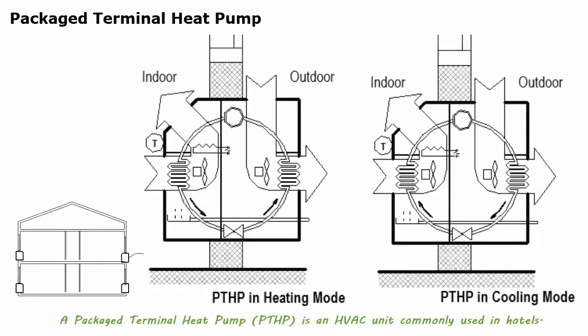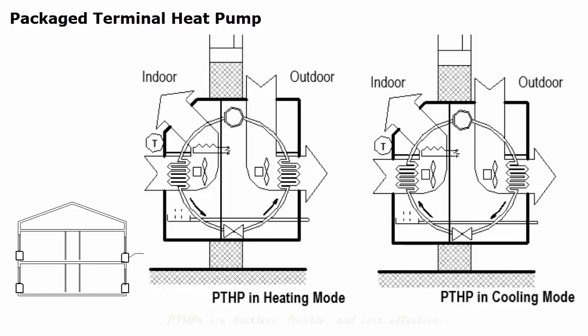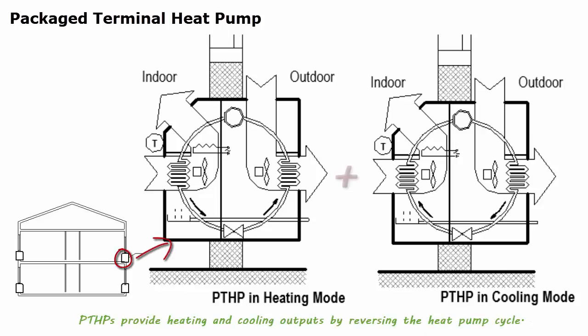A packaged terminal heat pump, PTHP, is an HVAC unit commonly used in hotels. PTHPs are ductless, flexible, and cost-effective. Similar to window ACs, PTHPs are installed through the wall below the window. They provide heating and cooling outputs by reversing the heat pump cycle.